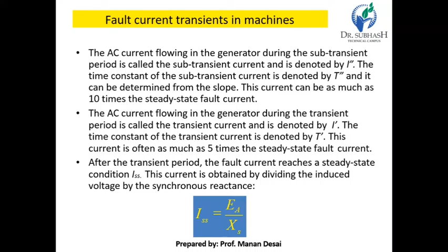Now, the symmetrical AC component of the fault current. As we see in the figure, there are 3 periods: the subtransient period, the transient period, and after the transient period, the steady state period will start. In the first couple of cycles after the fault, the AC current is very large and falls rapidly. That is the subtransient period. When the current falls at a slower rate, it is in the transient period. And when the current reaches its steady state value, it is in the steady state period.